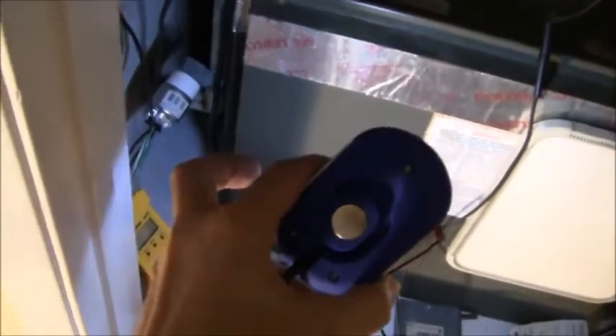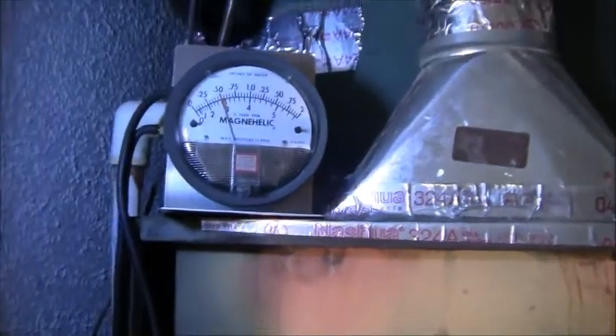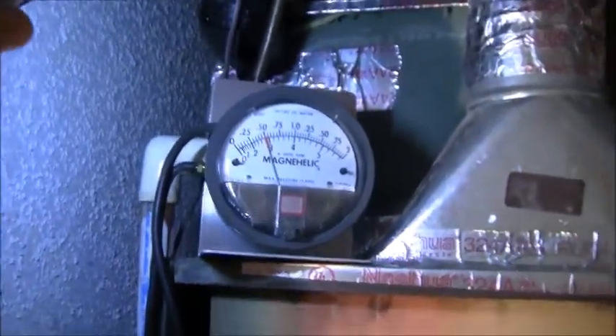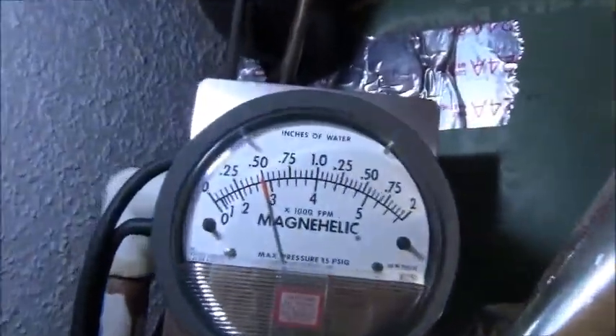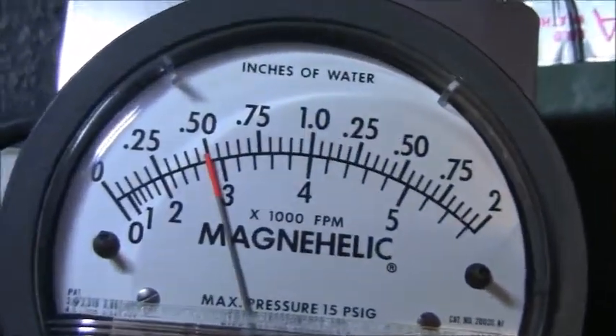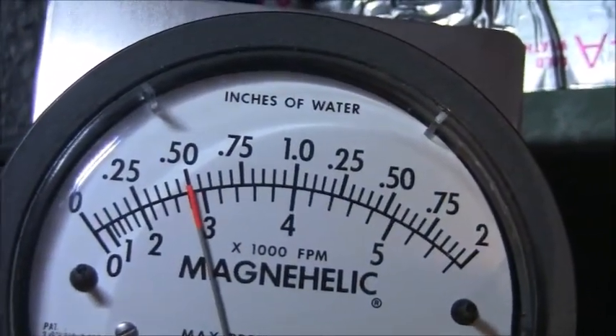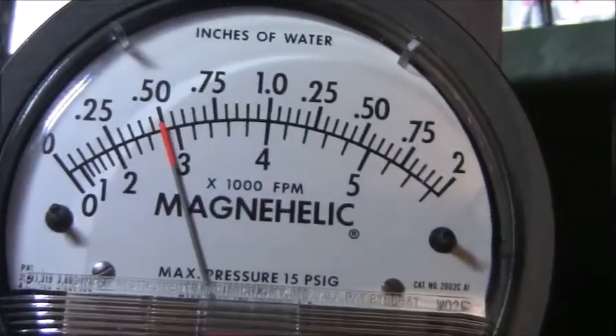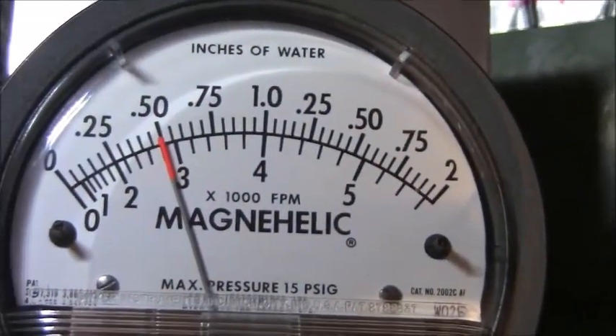Okay, I got the low port, which is the one there on the bottom, coming down, and I plug that into the side of the unit, which is after the filter. And then on the high side of the magnehelic gauge, which is the top line, I got that coming down, and that is plugged into right there, which is on the upstream side of the AC coil. There is your external static pressure on the magnehelic gauge. That is at 0.5 inches. That's a half of an inch of static pressure, water column. That is a good static pressure.